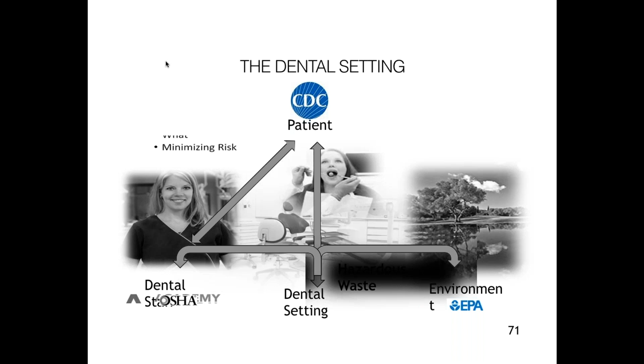So I'm going to skip the review questions because I want to just hit a couple of points to reiterate things. The first point I want to hit is the magic number for water lines, and that's less than or equal to 500 colony forming units of heterotrophic water bacteria. When it comes to sterilization, I want to hit once again the magic numbers from the CDC site, and that would be the area I would probably go to first: 250 degrees for a minimum of 30 minutes in a gravity displacement situation, and 270 degrees for 4 minutes for a pre-vac. If it's not a pre-vac, it's going to run up to 15 or 20 minutes.